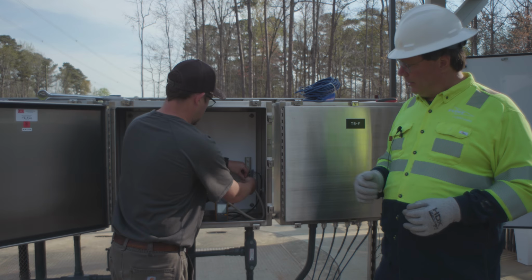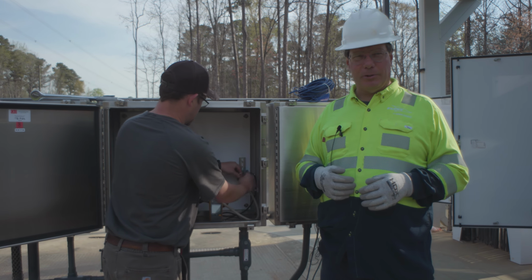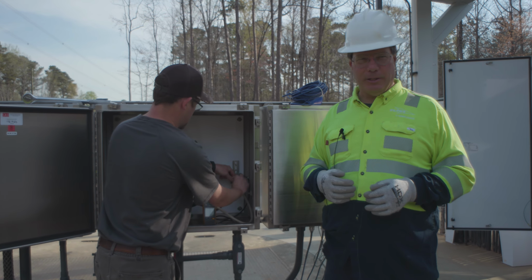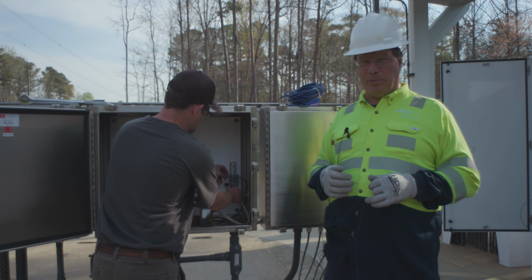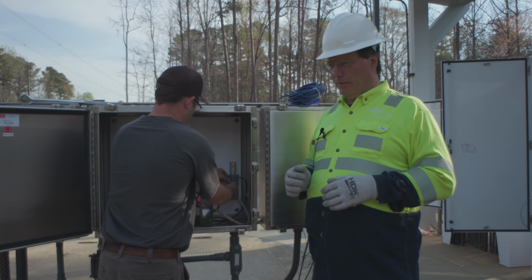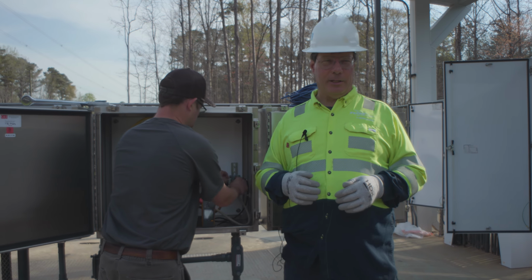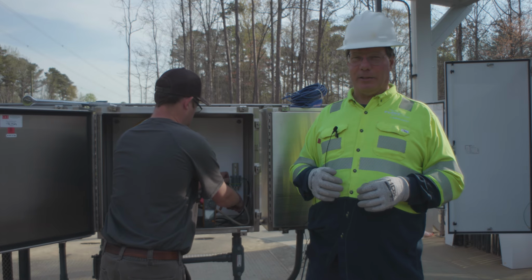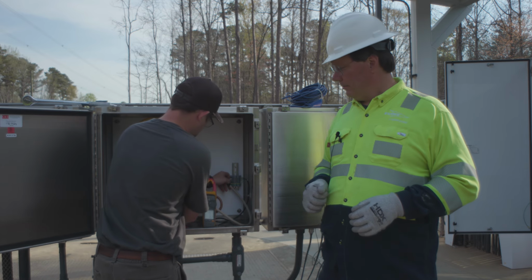It doesn't matter which direction you put it. 3 can go on 4 and 4 can go on 3 because it's a resistive circuit. It's not polarity. There's no polarity. For T1 and 2, there is polarity, so if you disconnect it, you have to put it back exactly the way you took it off.